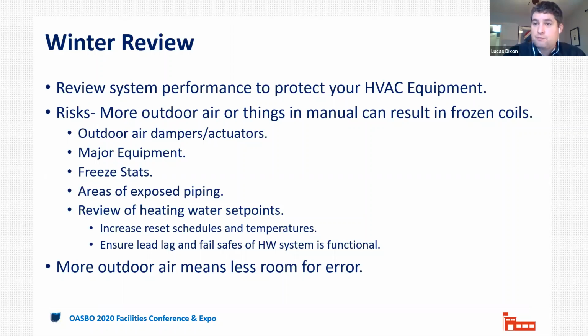And you just do the things, be especially vigilant, because you'd set yourself up to potentially expose things that haven't happened in the past. I think overall, how we're thinking about this is that with more outdoor air coming into your building, there's less room for error. So if you have limped along with one hot water pump for a couple of years, just haven't gotten around or haven't gotten it funded for fixing that hot water pump, that secondary pump, now's the year to get it fixed so that you have that fail safe. Go through and manually shut off your lead pump. Make sure and watch the secondary pump come on. Things like that are best practices you want to do before you find out that that sequence isn't working for some reason.